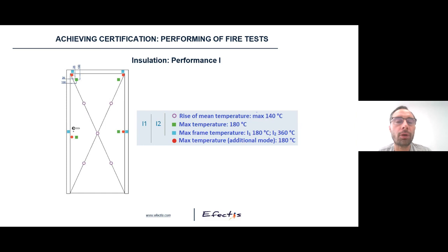And in order to assess this higher performance, we use thermocouples that we put on the unexposed side, and we have limits of temperature not to reach. This temperature is 140 degrees of mean temperature on all the leaf, and 180 degrees at 100 millimeters from the edge of this leaf. For insulation, there is a specific thing for doors, which is two different levels of insulation, which is I1 and I2. To be quick, I1 is used only in Belgium, so manufacturers who want to sell their product in Belgium have to comply with I1 performance, but it is the only country in Europe that uses this kind of classification. For all other countries, it's only I2, which means thermocouples are placed at 100 millimeters from the edge of the door.